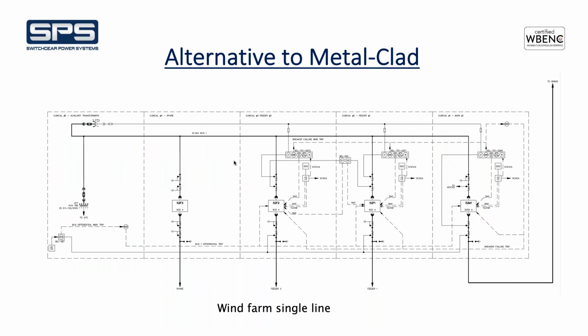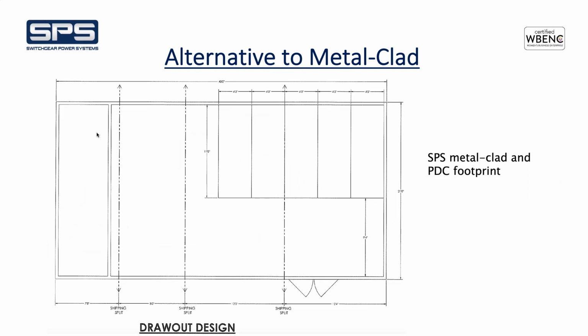So here is a wind farm single line for a project that we built last year. And this is what was specified initially. It is draw out metal clad switchgear, the station service transformer, and some other protection ITs. So it came out specified as draw out metal clad switchgear. And we bid at draw out because, as I mentioned, we know that not all of our customers want fixed mounted metal enclosed. Some of them still prefer draw out. And this was the footprint that we developed for the metal clad design.